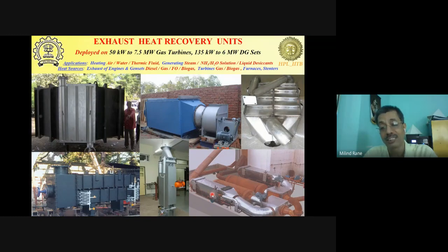By the way, this installation was in Chennai in a 5-star hotel and installed on 2000 kVA gensets. This was the muffler of that genset, and these are the heat exchangers with insulation. So you can see that the actual heat exchanger inside core would be much smaller. And this was producing steam at around 10.5 bars, 10.5 kg per centimeter square gauge, at around 186 degrees saturation temperature, and then that steam was used to operate a double effect LiBr system to produce air conditioning for this. And there were two of these units sitting side by side here.